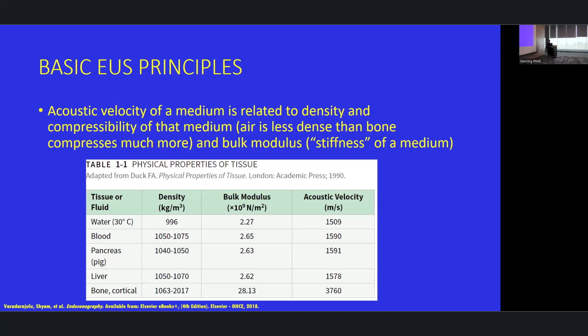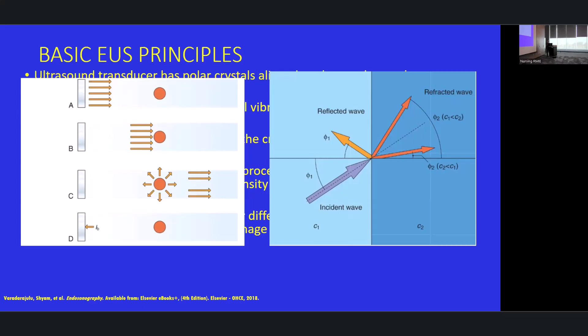The transducers on an ultrasound probe have polar crystals that are aligned to change shape when an electric field is applied. This change of shape causes mechanical vibrations of these crystals that generate a sound wave. That sound wave travels through a medium, hits an item of interest, such as a tumor or the liver or the pancreas, and bounces back. It hits the transducers and deforms the crystals, which creates another energy form, electric energy, that goes to our processor. That energy impulse, created from the distortion of the crystals, allows for image generation on the processor.